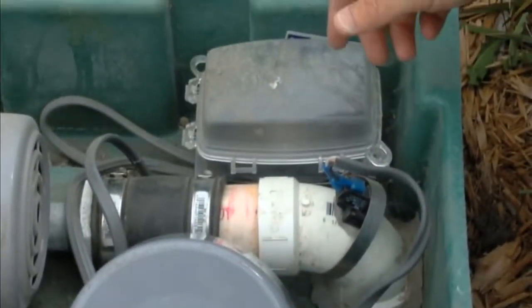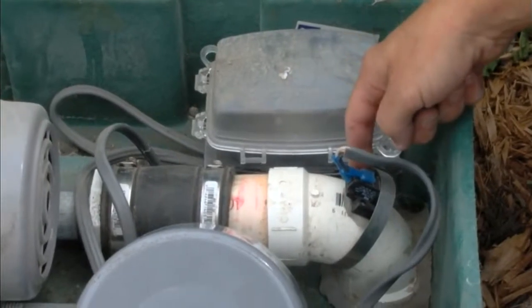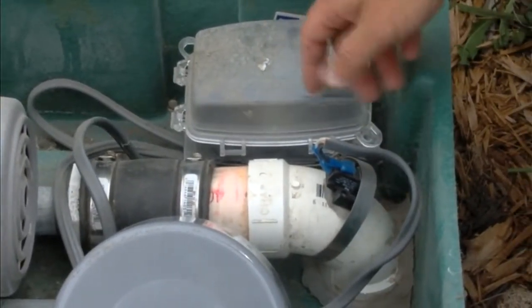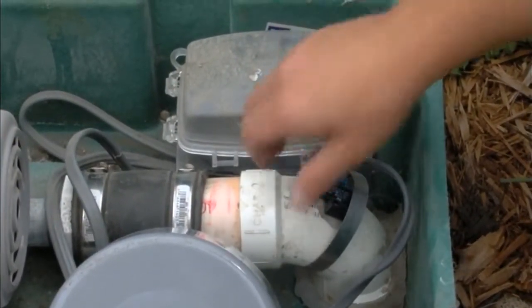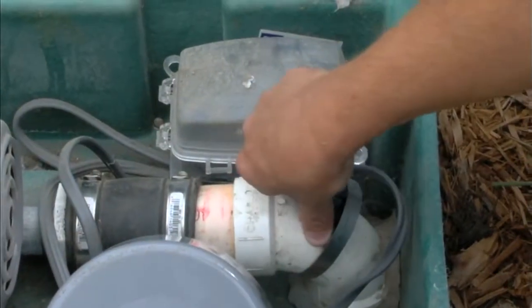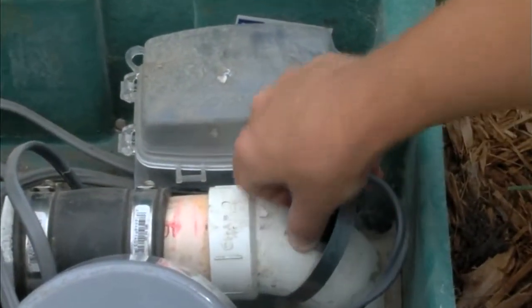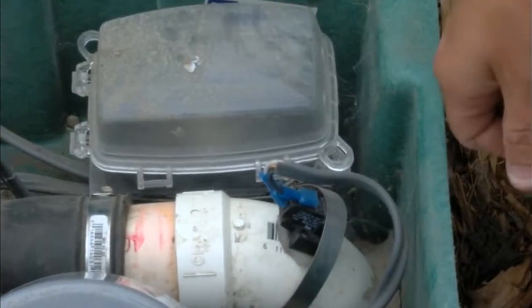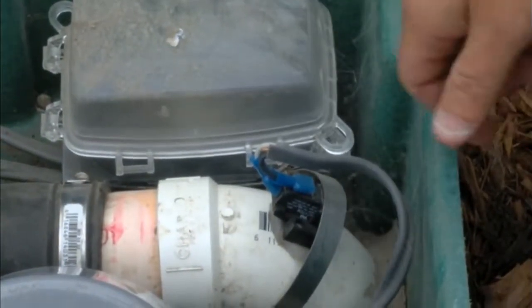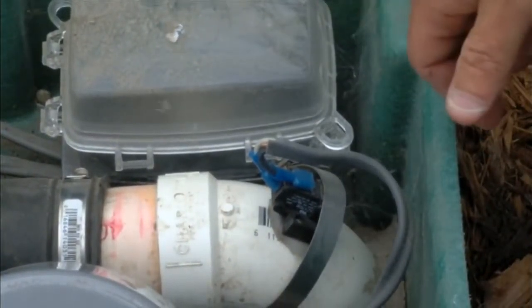Nothing on this one. We also have a pressure switch for detecting high water level in the system. That's on the outlet pipe of the blower. Just real quick, put your fingers, your hand around that switch just to make sure it's in there. Probably give it a little wiggle, make sure it's in there nice and tight. It's a low voltage switch, so you can do that while the power is on if you prefer.